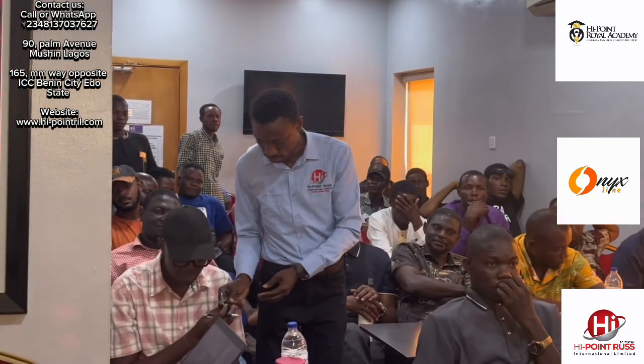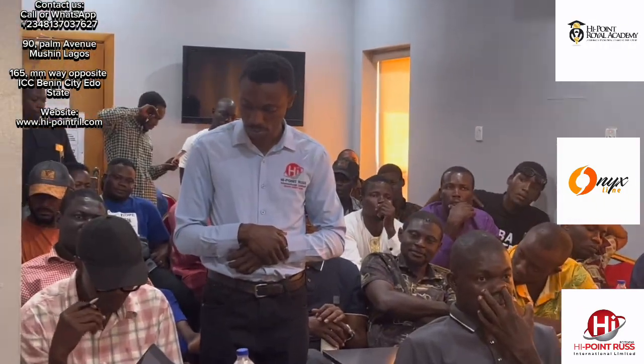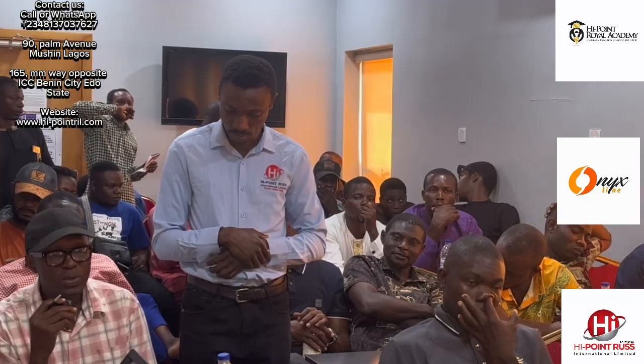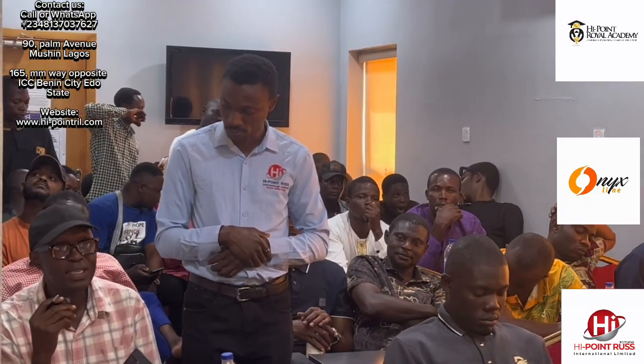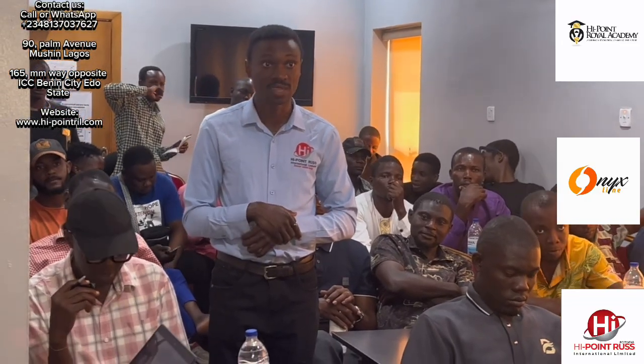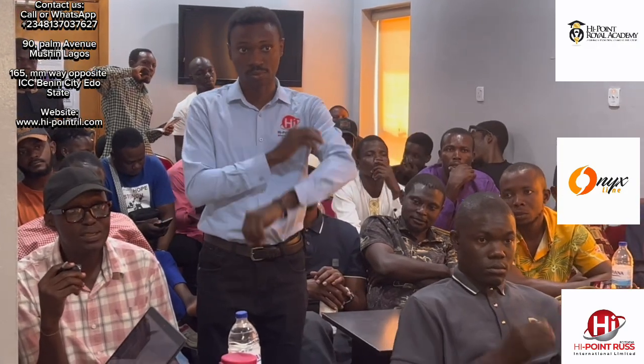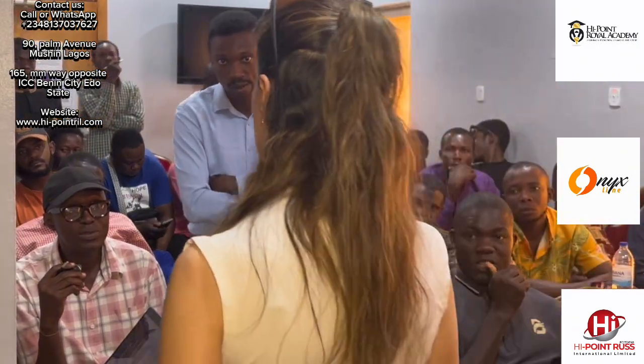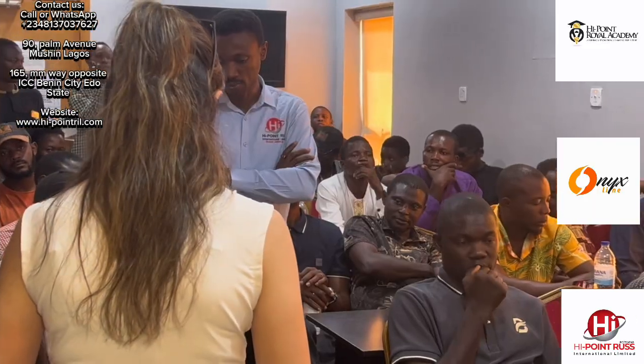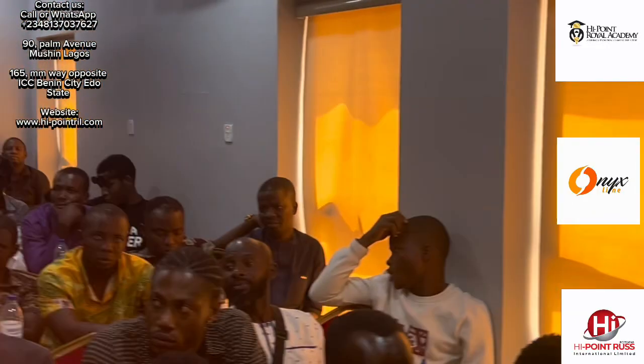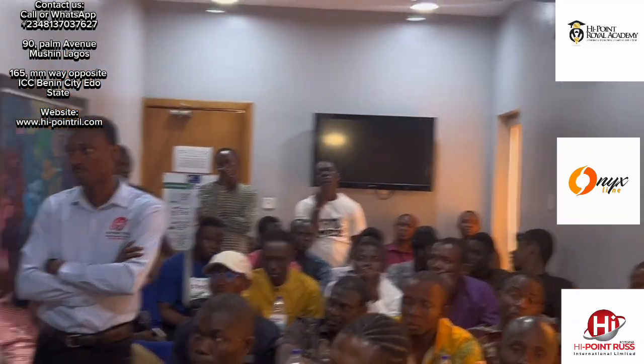Made mention of the DOD of 6,000 cycle, which is 95%. The DOD, yeah, 95. What is the level of the discharge that will be? 5%, the level of discharge. Yes, you can reach 5%. But for me as an engineer, I don't prefer to reach 15%.